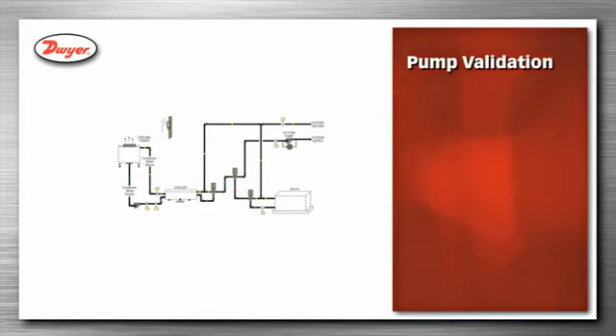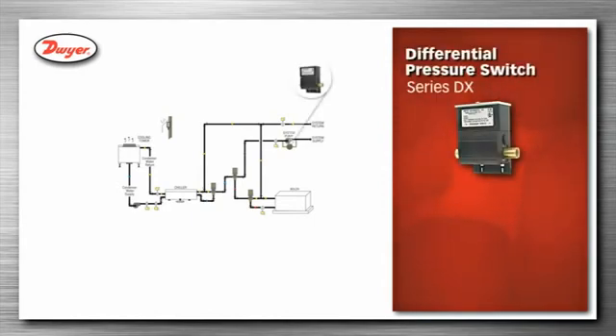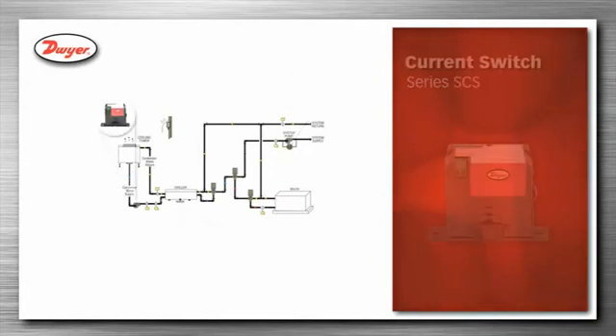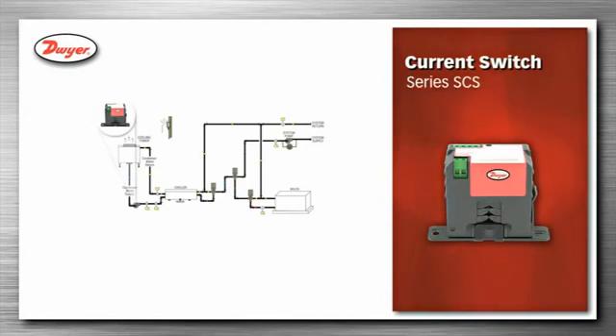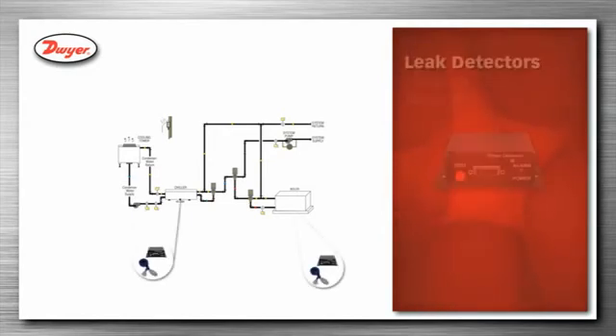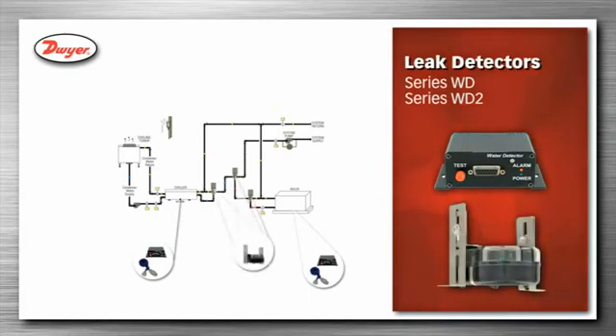Dwyer offers several products that can be used for pump validation, proving that the pump is operating and there is water flow. A differential pressure switch, series DX, or a differential pressure transmitter, series 629, can be used by monitoring the differential pressure between upstream and downstream of the pump. Series SCS current switch can be used by monitoring the current usage of the pump. Paddle flow switches, including model FS-2, series V8, or series V7, can be used by monitoring the water flow exiting the pump. Series WD and WD2 leak detectors are used to detect leaks of fluids around equipment and valves or to detect full drip pans.